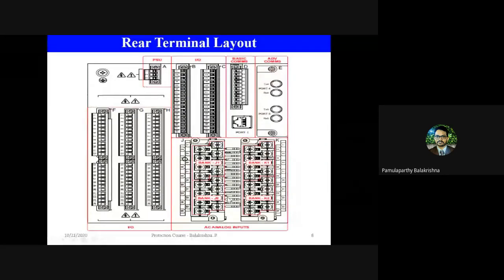So it is designed in a flexible manner in such a way that you can remove any card. For example, if I don't require this slot card, I can simply remove it, and if required, I can place it back at any point of time. Here I have four banks. If I want all four as currents, I can keep it. If I want one voltage and three currents, I can keep it. If I want two voltages and two currents, I can keep the corresponding card. So this design enables modularity, and at any point of time you can either replace or keep back any of the cards that you require for your protection purpose.